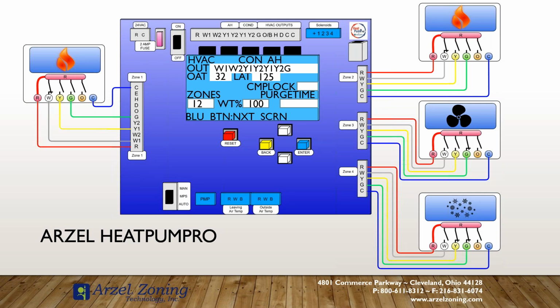So we can have thermostats all calling for different things: fan calls, heating calls, cooling calls. The Arzel panel applies a set of rules and determines what we're going to send to our equipment so that we aren't damaging our equipment with conflicting calls. When we look at the Arzel HeatPumpPro, there's that line that says out. That line that says out tells you exactly what's going to your equipment. So for this one, I have it showing what you would typically see for an all-electric application with all 4 stages calling. We see W1, W2, Y1, Y2. So that's compressor, first and second stage, Y1, Y2, as well as first and second stage of our backup heat. We can see our blower running at high speed with air handler Y1, Y2, and we have that G call going to the equipment for the fan operation.